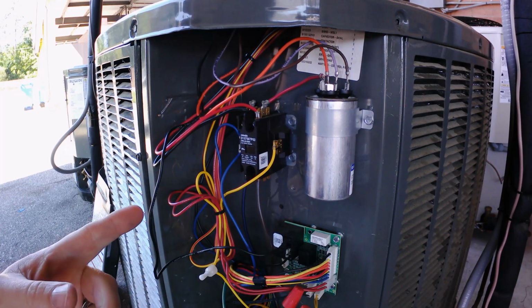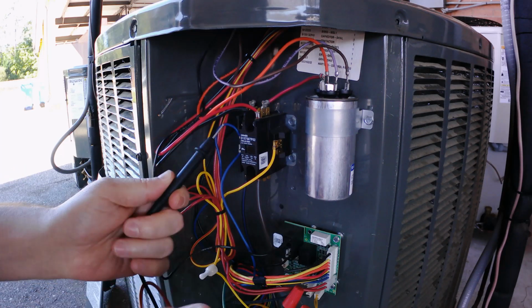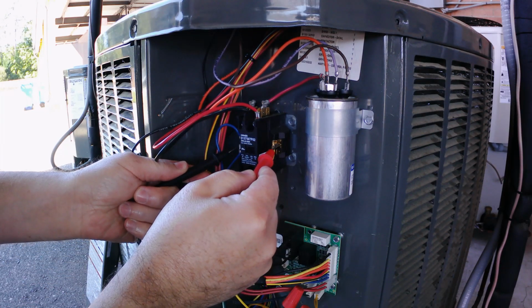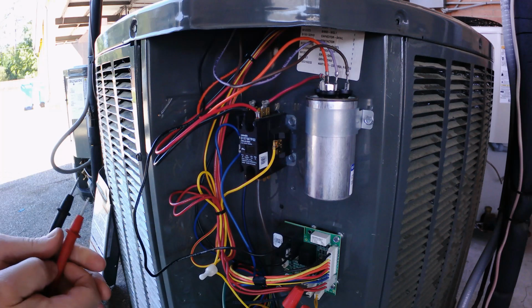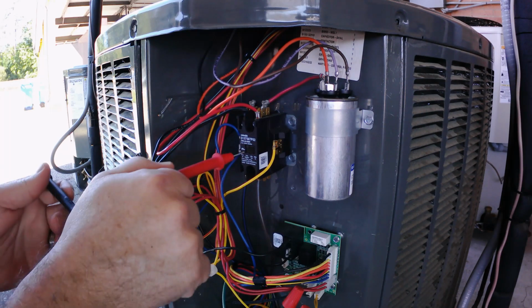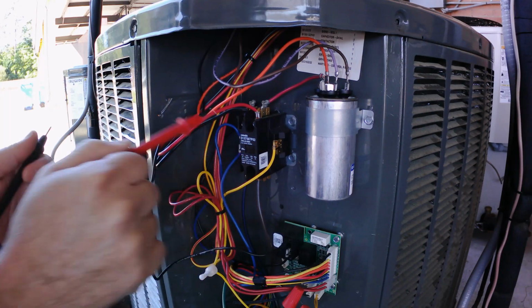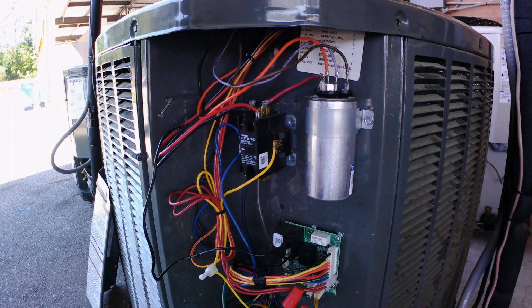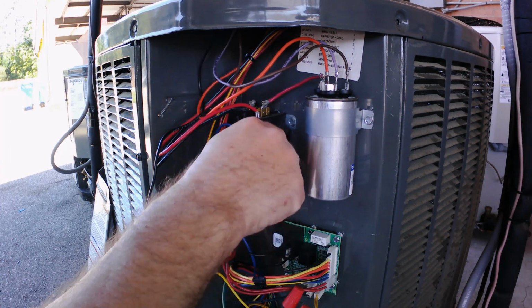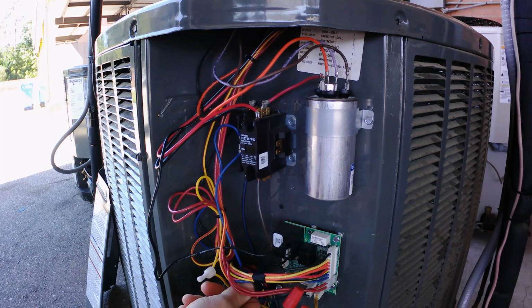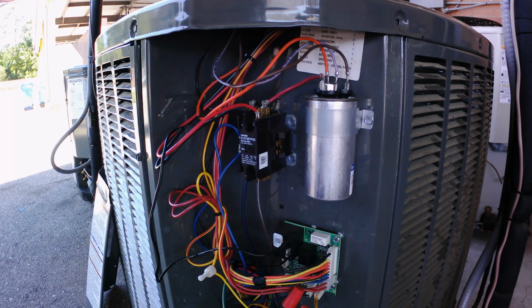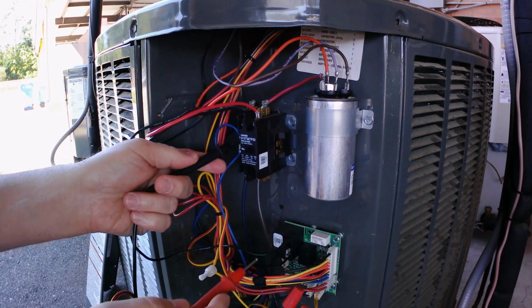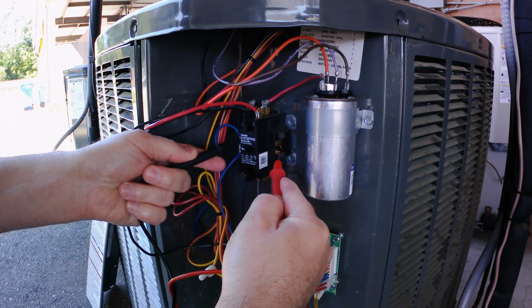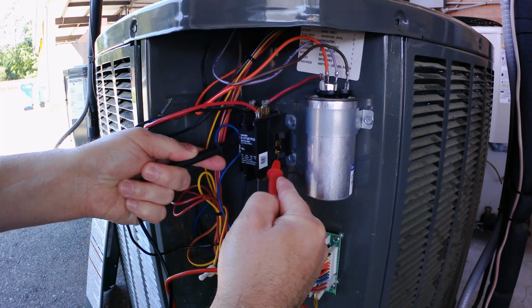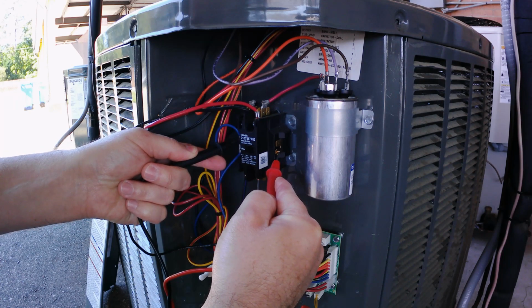All right. If you have 24 volts to the side of this contactor energizing the coil, and the switch here isn't pulling in, then the easiest thing to do, since you're right here, is to pop off one of the leads on the side, switch your meter over to ohms or continuity, and check the side of that coil for a resistance reading. In this case, I get 14.4.